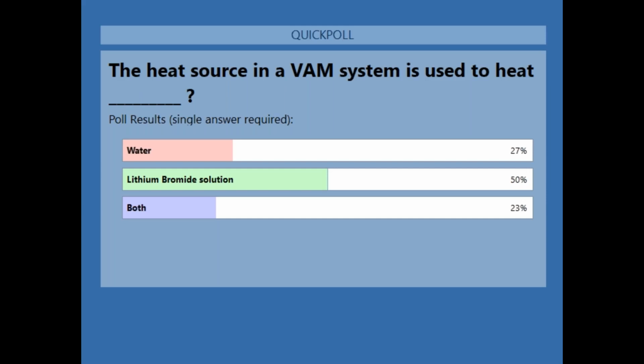The heat source is used to heat the lithium bromide solution, which returns back to its concentrated state so it's ready to absorb water vapor again, continuing the cycle. The heat source is not used to heat the water directly. Water converts into vapor because there is vacuum in that vessel, called the evaporator.